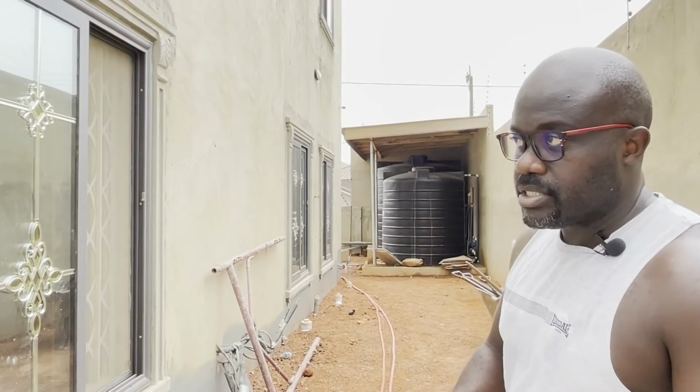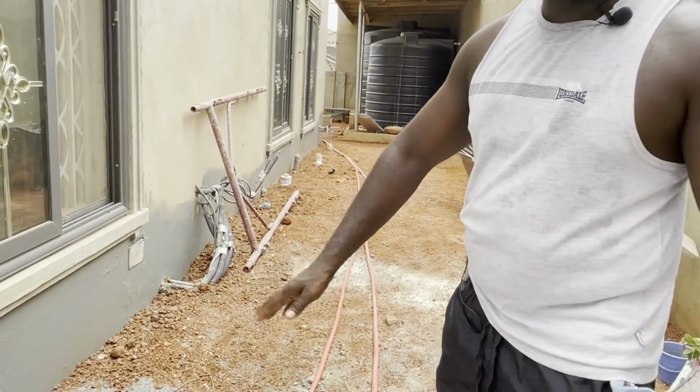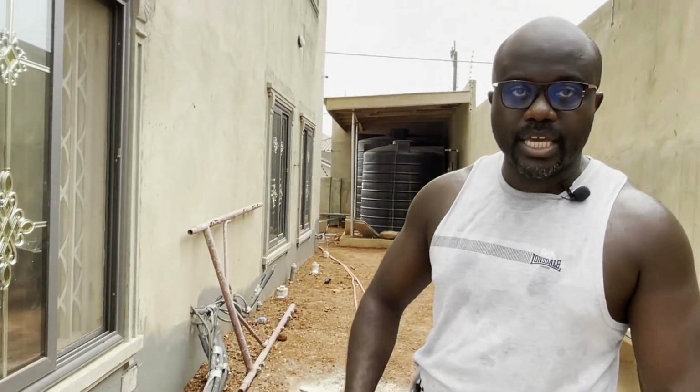Depending on your budget and your finances, at every stage, when you're digging the ground and you put in your main building earthing, your generator building earthing, and you know you're going to put in a lightning protection system, and your priority and budget will allow at that point in time, put it in at that point in time. That's the easiest thing to do. We obviously haven't done our permanent landscape, so it's still not a huge issue. There's no permanent landscape on here, so that is absolutely fine. We'll just dig it and put it in.